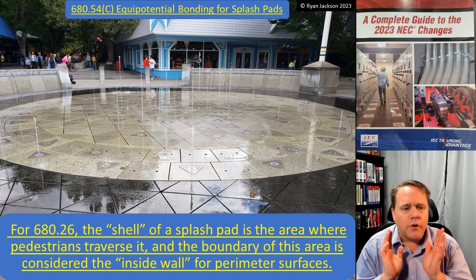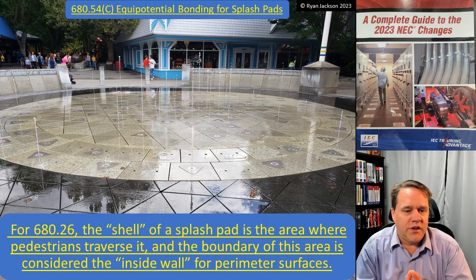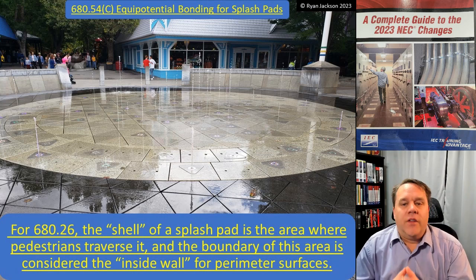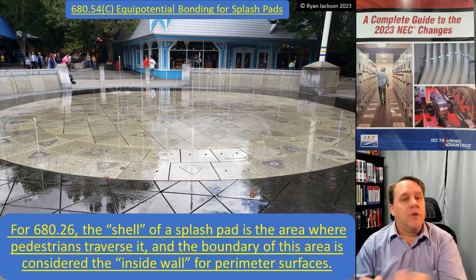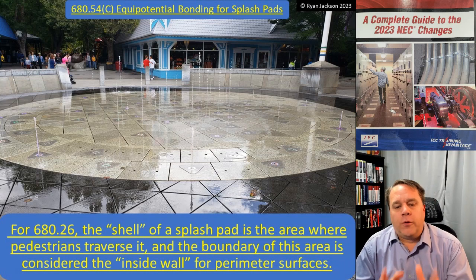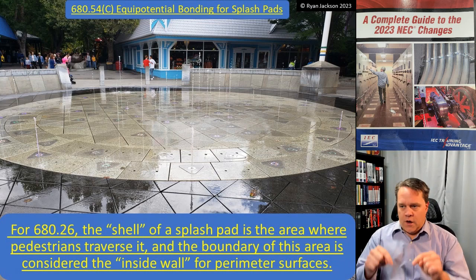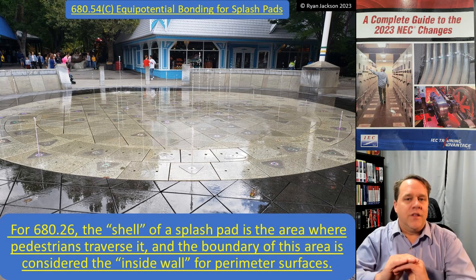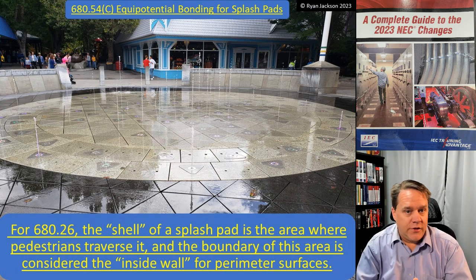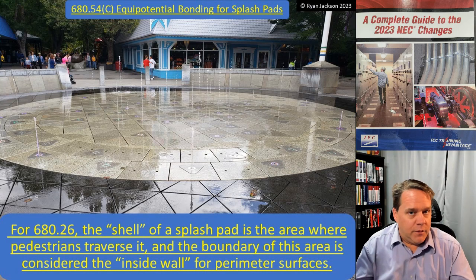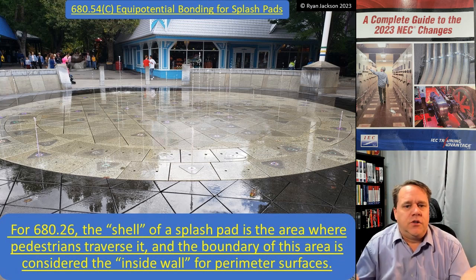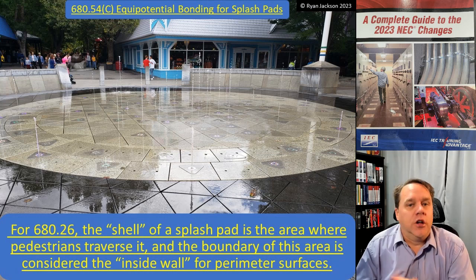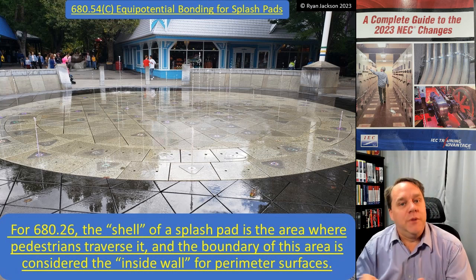For the purposes of 680.26, the shell of a splash pad is the area where pedestrians traverse it, and the boundary of this area is considered the inside wall for perimeter surfaces. Wherever the people walk, that's the shell — go out three feet, that's the perimeter surface. Bond all of that together, probably using rebar in the concrete, then bond that to the motor or anything electrical within five feet of the area, and you're good to go.